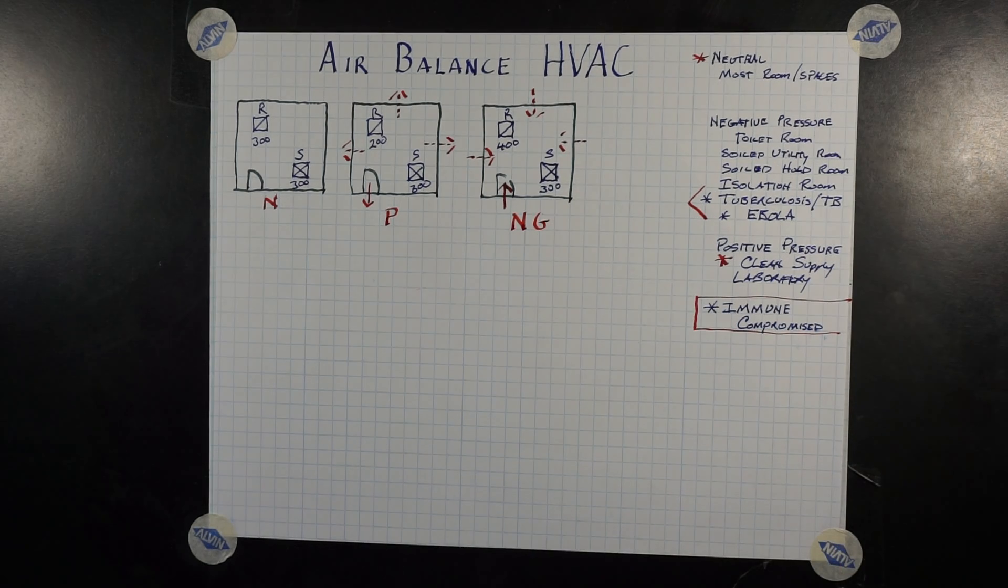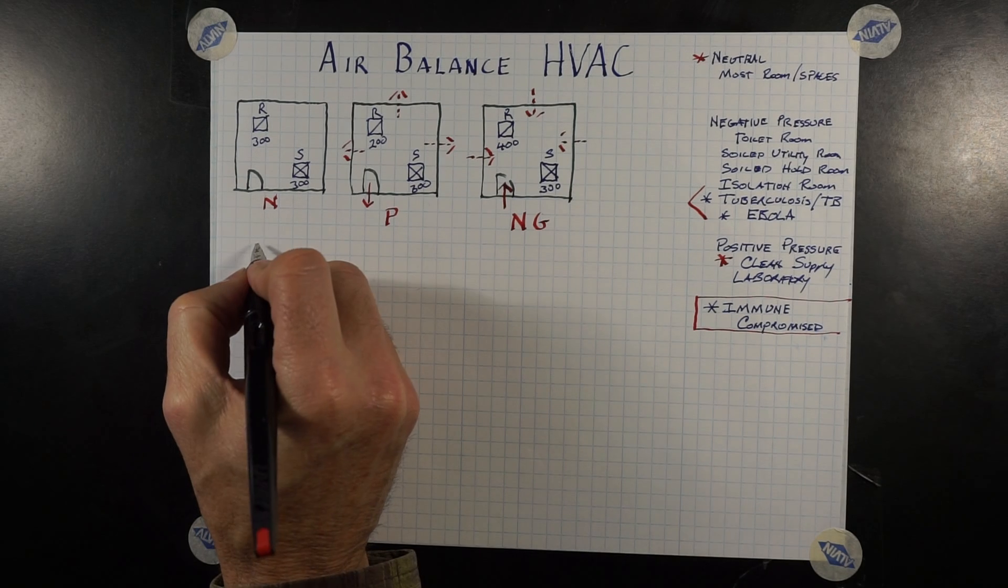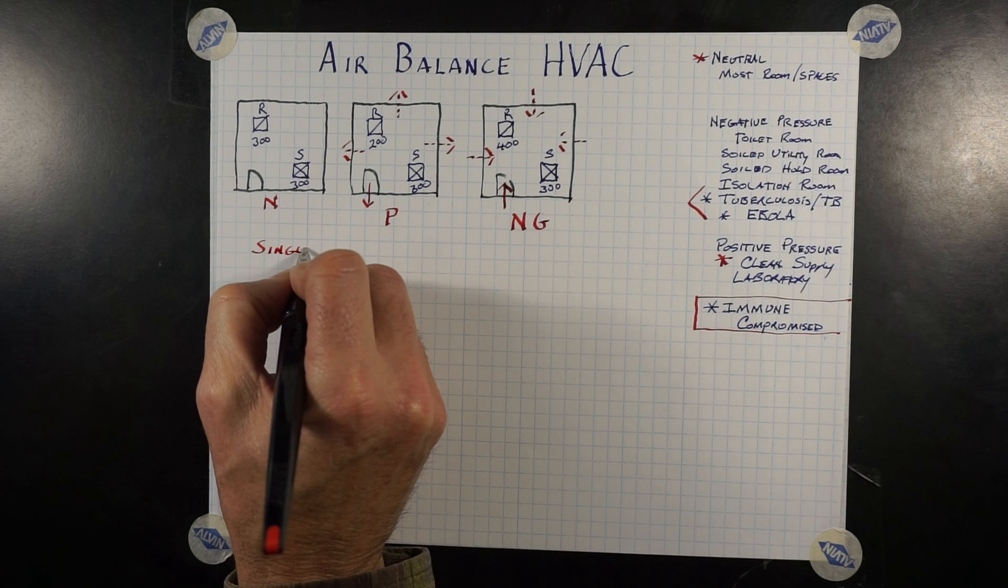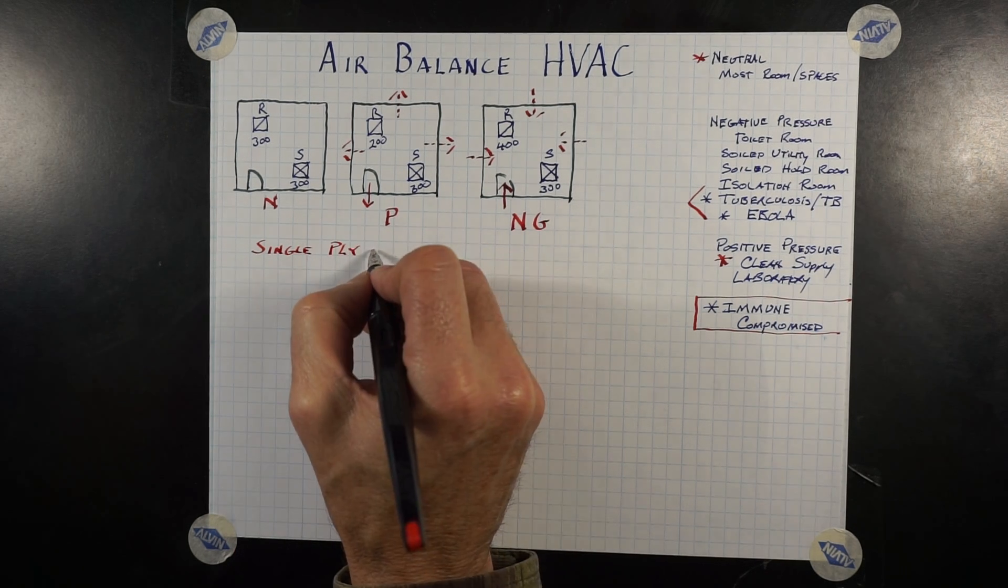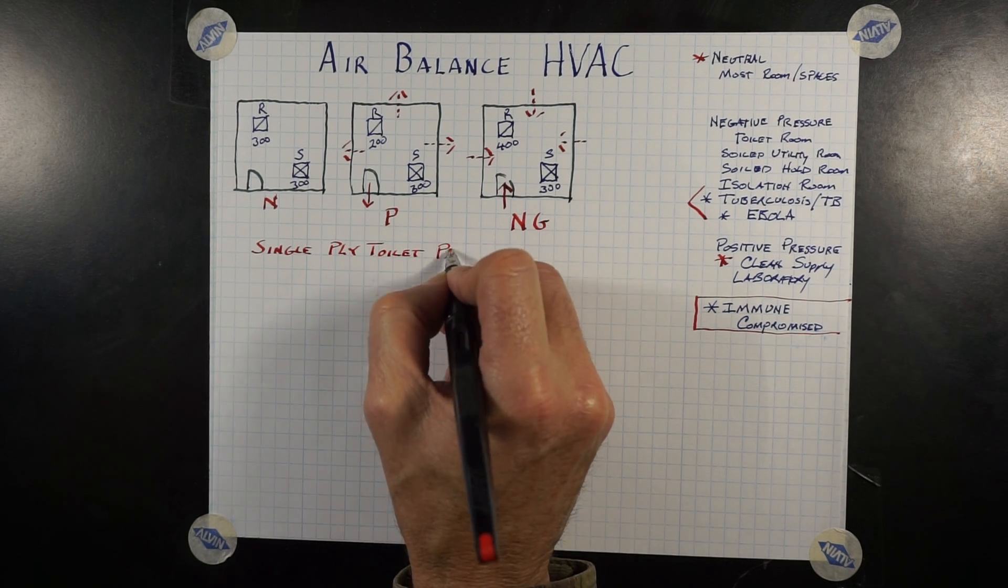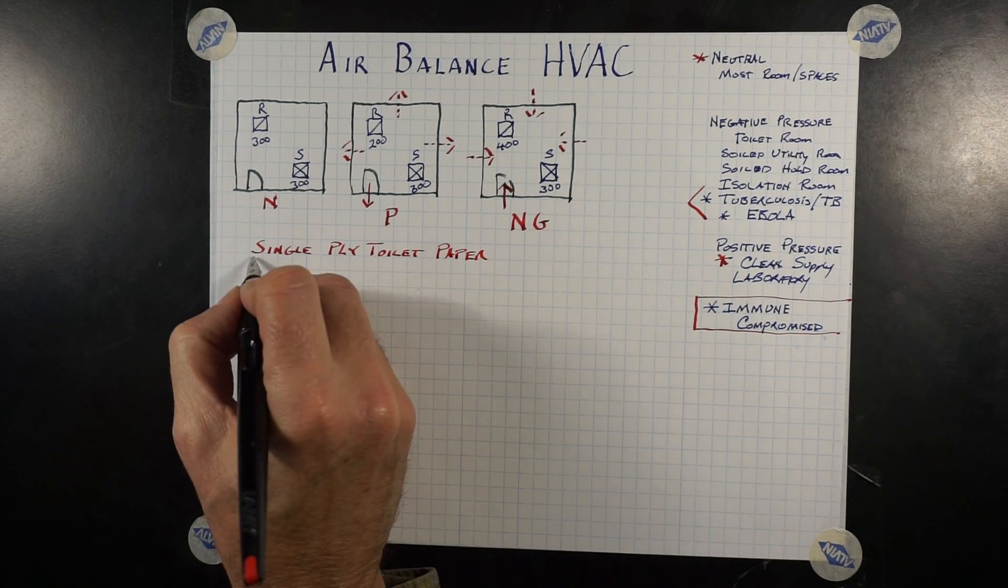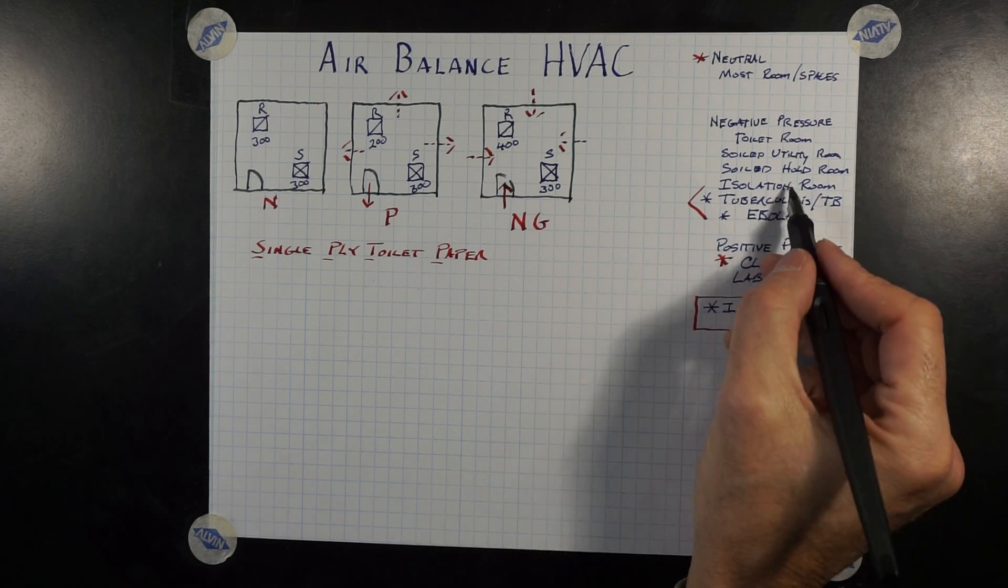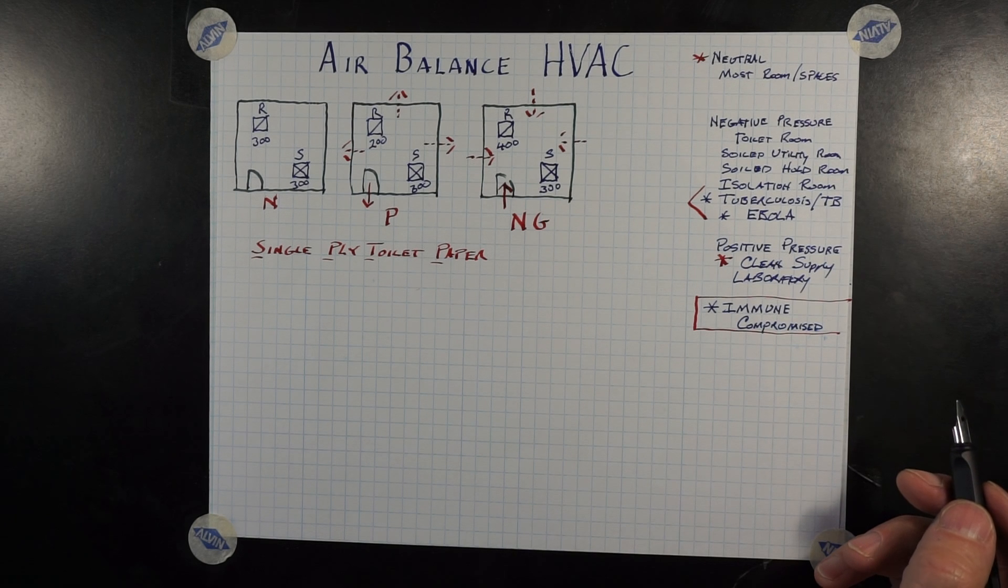In relationship to toilets, our rooms are negative pressure. Therefore, any odor is being exhausted outside. A great way of applying a test to see if the room is neutral, positive, or negative is the single-ply toilet paper test. Separate one sheet so you have a single-ply toilet paper, have it two or three squares long, and open the door slightly and hold the toilet paper at the edge of the door.